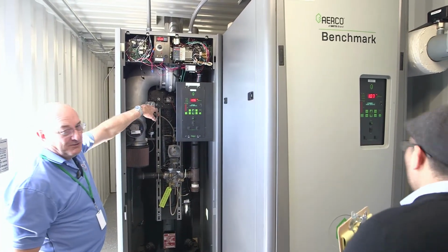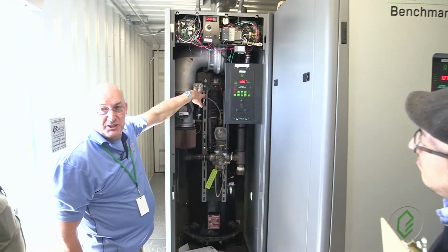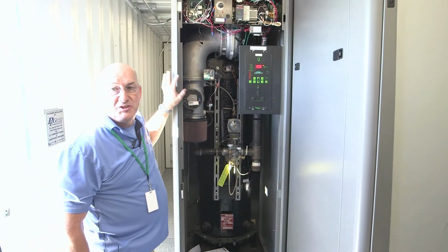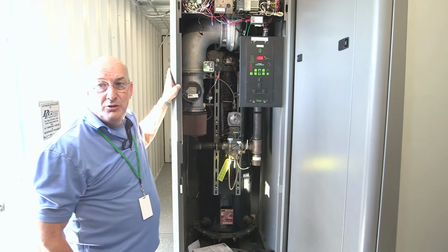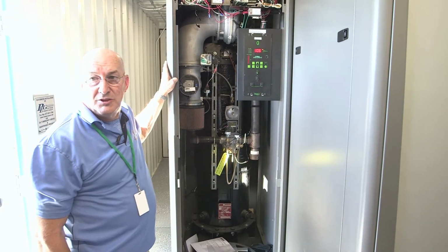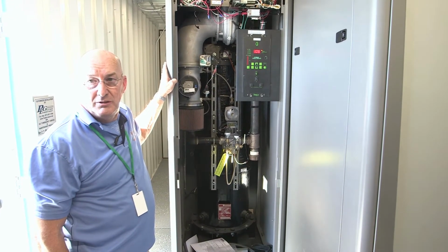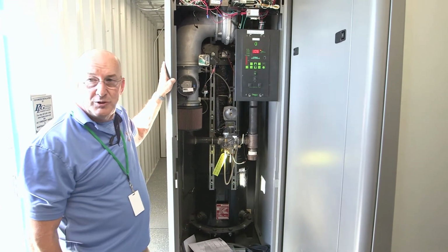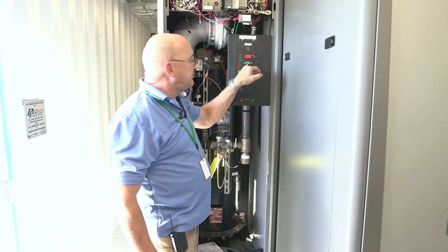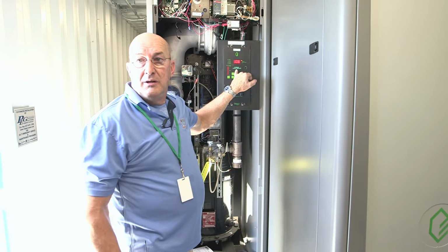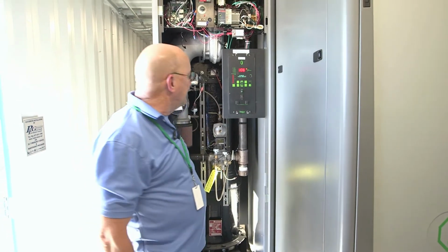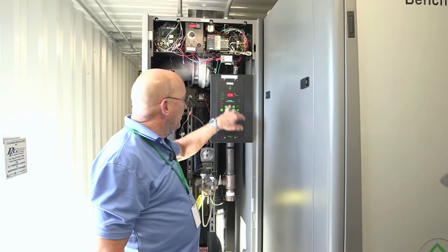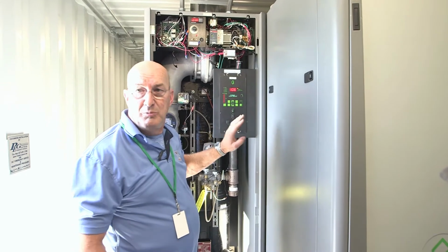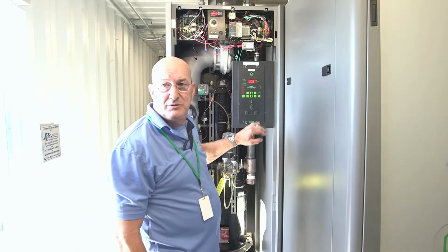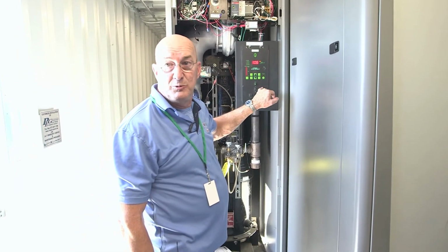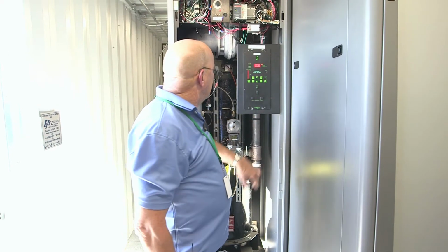Or if you're used to having gas before, you have gas pressure switches. These are non-resettable. You can't reset these. There's no sense taking the panel off to try. Because if it tells you low gas pressure, it's going to tell you low gas pressure on the display. And when it tells you low gas pressure, or low water, whatever, you know the boiler's not running. It's in fault, because it'll say fault, and it'll tell you exactly what the fault is. All right? So you walk over here.